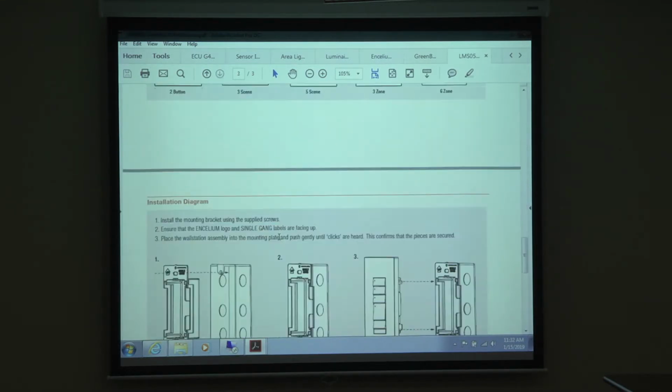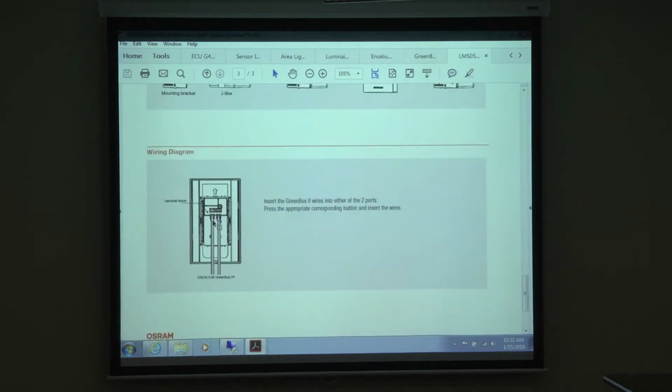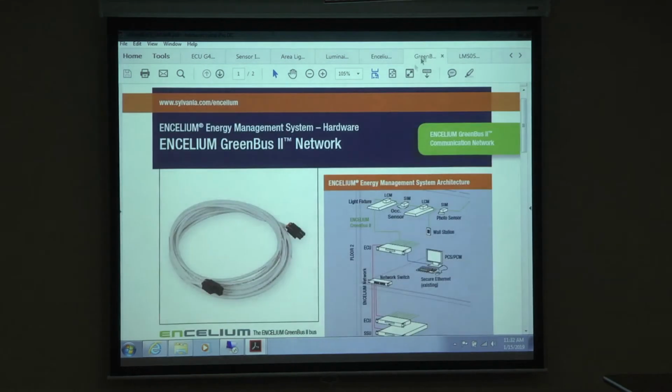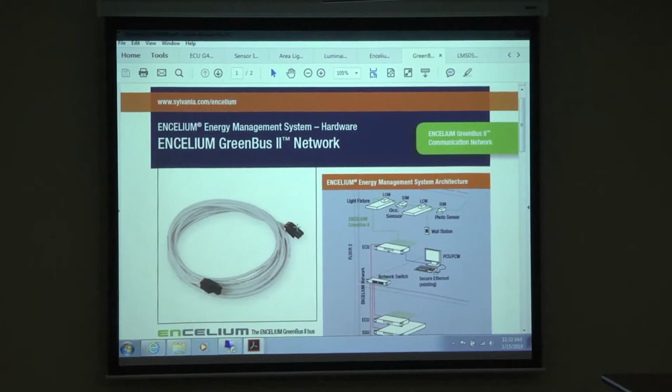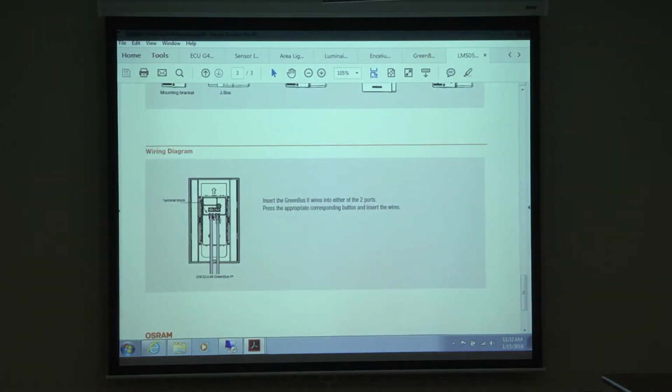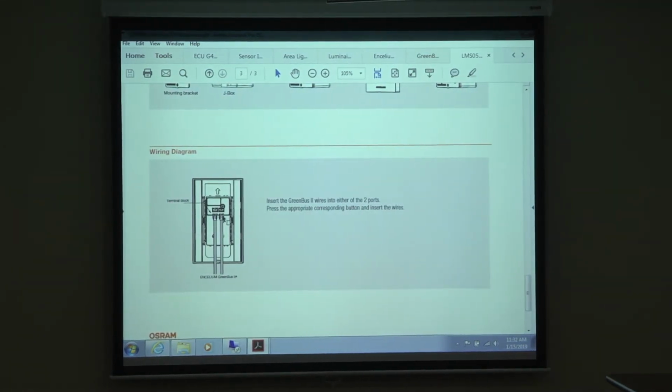And these are connected with the GreenBus cable. In this case, this connector is taken off, so there's a strip that ends the cable alone. The bare wire, stranded cable, is plugged directly into the back of these switches. So in on one side, out one side, and that's how you put it in the daisy chain, right? That's how you control those buttons.